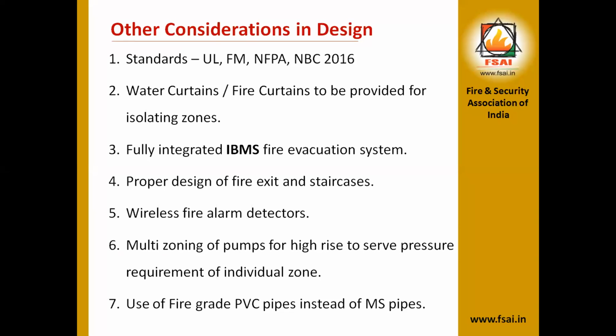Proper design of fire exits and staircases, wireless fire alarm systems, and multi-zoning of the pumps for high-rise buildings to serve the pressure requirements of individual zones. If the pressure requirement of each zone is different and multiple zones are provided, then the requirement can be met very easily to protect the lives of the people. Use of fire-graded PVC pipes instead of MS pipes. Fire-graded PVC pipe will burn later.